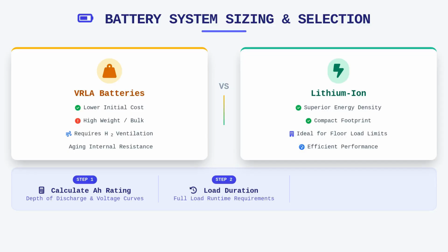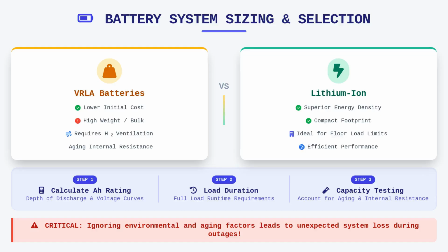Keep in mind that as VRLA batteries age, their internal resistance increases, which necessitates periodic capacity testing to ensure they can still deliver the required current during the final minutes of their rated runtime. Failure to account for these environmental and aging factors will almost certainly lead to an unexpected loss of systems during a prolonged outage.